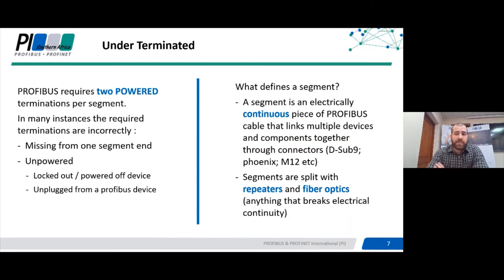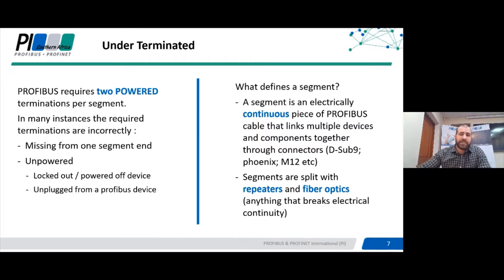Terminating resistors are enabled to prevent these reflections. Profibus typically requires two powered termination resistor circuits per segment. These resistor circuits are built into Profibus connectors and some devices, and you enable them by turning on a simple switch on a connector or on a device. Connectors are typically sub-D9 connectors, Phoenix connectors, or M12.